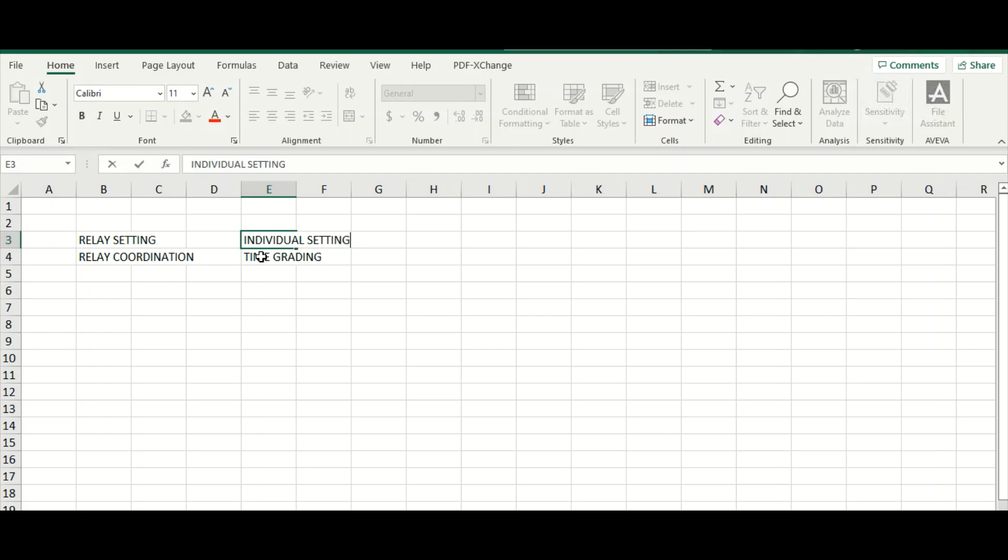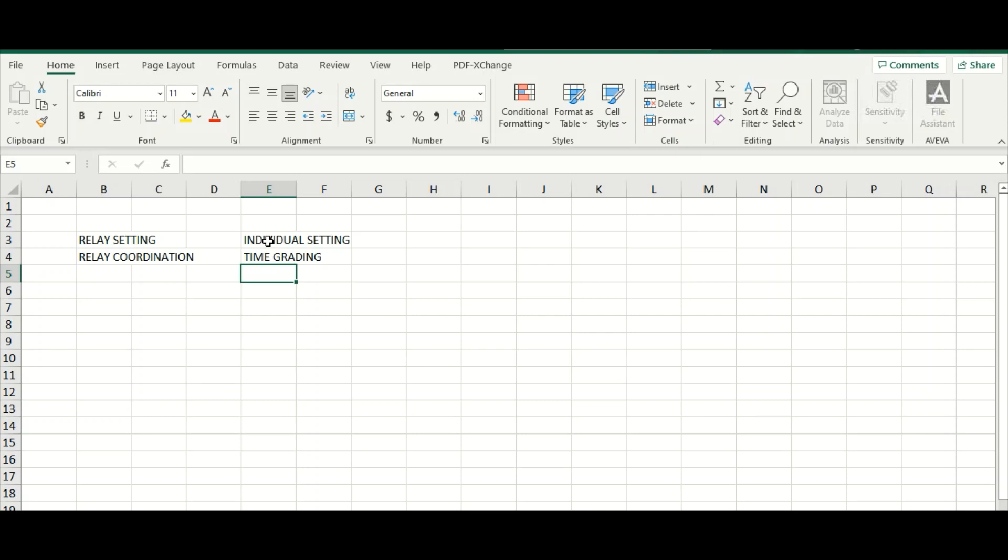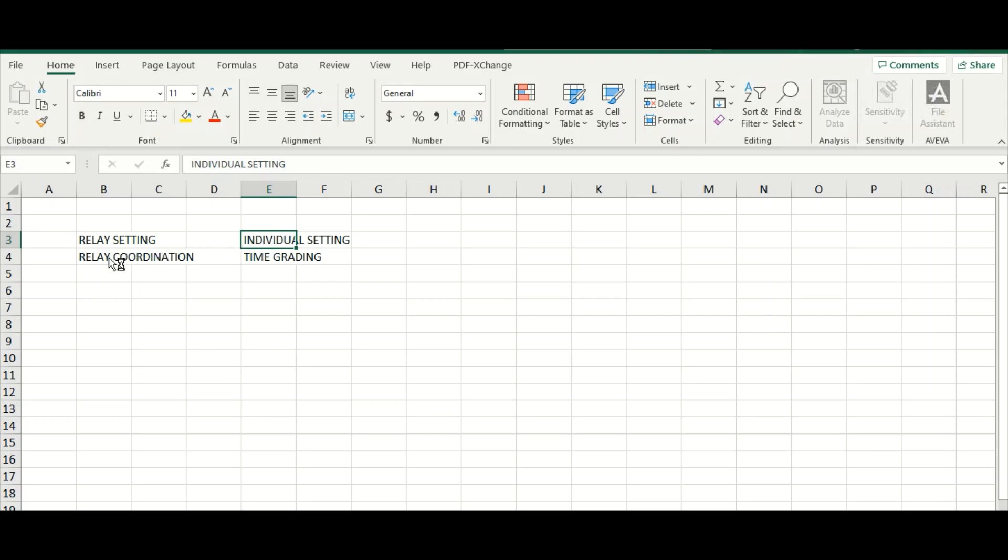So first of all, based on the current, based on the continuous current flow, considering the margin or the short circuit current, firstly you need to specify the relay setting—each individual relay setting. That means each component, suppose 50 instantaneous, 51 IDMT—these relay settings. And after that you need to proceed for the relay coordination, which is the coordination or the time discrimination or time grading.